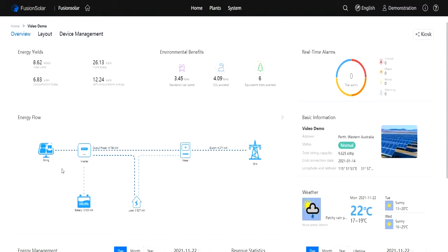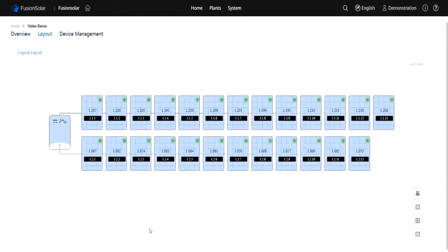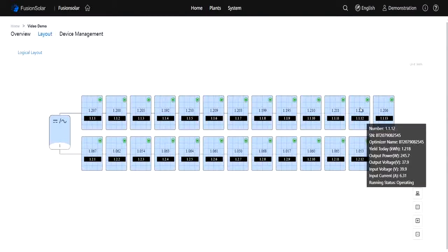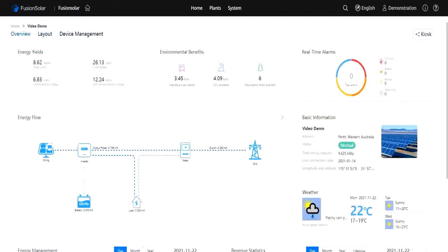This customer has 25 optimizers, and he's got a 5 kilowatt inverter. He's oversized it up to 9.625 kilowatts of panels, which he's allowed to do, as I explained earlier in the video, because he has the battery. He's also got optimizers on every single panel. If you hover over the optimizers, you can see the details. This panel with its optimizer has produced 1.218 kilowatt hours of power today. So all very nice.